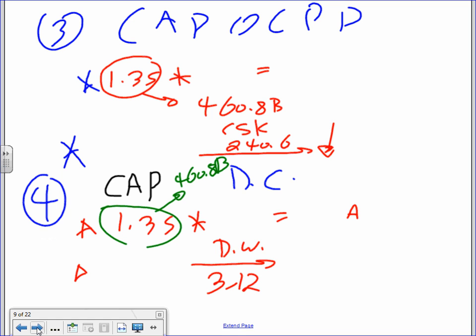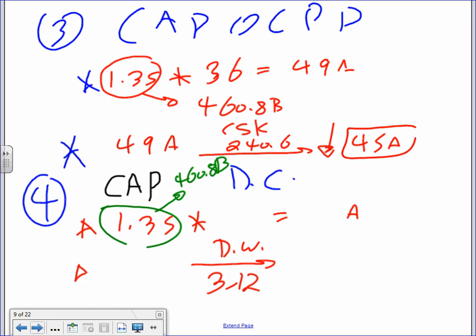Next, the overcurrent protection device. We just did that. So where are we here? Okay, so we got number 3, the overcurrent protection device. The same thing, guys, 36 based on your friend Chad, 36. You multiply, you get 49 amps. You take the 49 amps, put it in table 240.6, and that'll get you 45 amps. You go down, you don't go up on the overcurrent protection device.